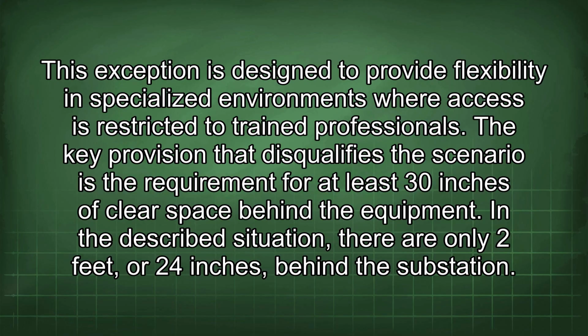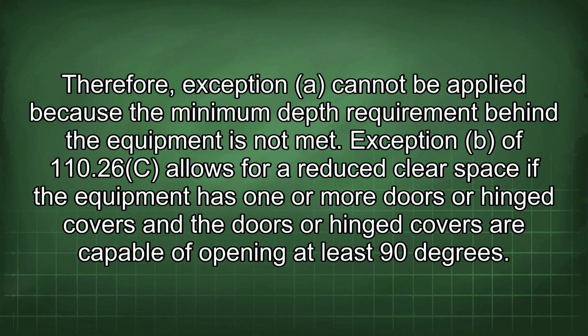The key provision that disqualifies the scenario is the requirement for at least 30 inches of clear space behind the equipment. In the described situation, there are only 2 feet, or 24 inches, behind the substation. Therefore, Exception A cannot be applied because the minimum depth requirement behind the equipment is not met.